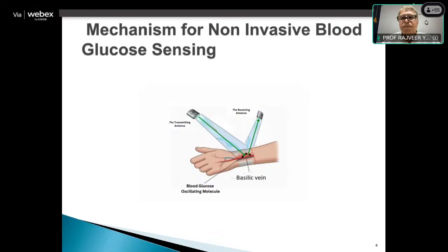as a wavelength specific, which we got from the research that the wavelength of the blood glucose molecule corresponds in this particular range. So that we create resonance, and from this resonance we create absorbance phenomena, and from this absorbance phenomena we compute the blood sugar level, or say blood concentration.